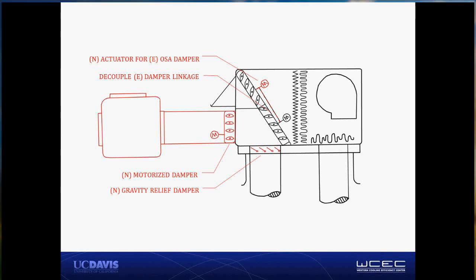One of the unique pieces of this design is that we decoupled the return air damper from the outside air damper and added a new actuator on the outside air damper so that we could allow the unit to operate in economizer mode during those periods when the indirect evaporative cooler is not able to maintain all the room cooling conditions, or when indirect evaporative cooling isn't needed, say in the heating season when the system has been winterized and shut down. In that scenario, you still need to provide ventilation air to the space, and so we needed to make sure that we had access to that outside air through that outside air damper.